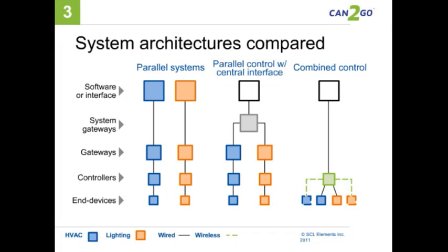But with modern systems, now what we can do is basically combine the HVAC and lighting end devices, and then combine all that into one single controller, and have this controller also act as a gateway so it can talk directly to your building management system. So as you can see, there are a lot less boxes, a lot less wires, and just less complexity, fewer maintenance issues, et cetera.